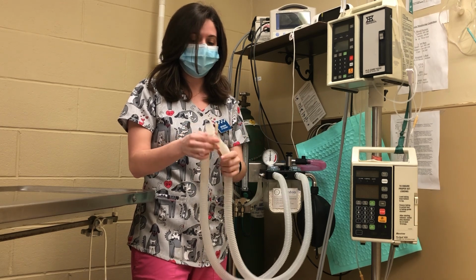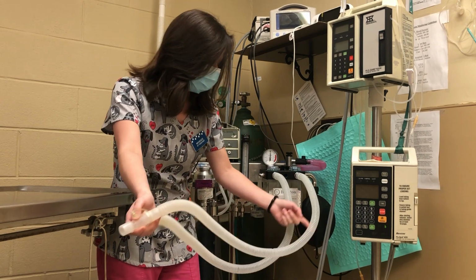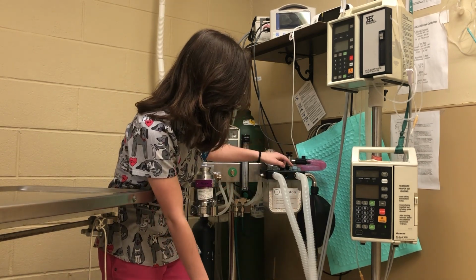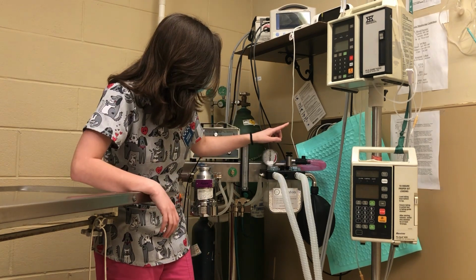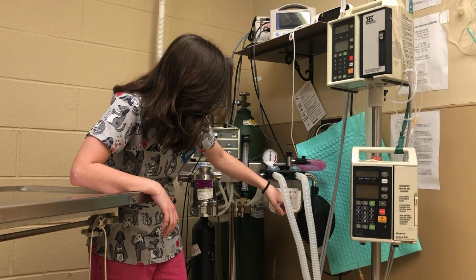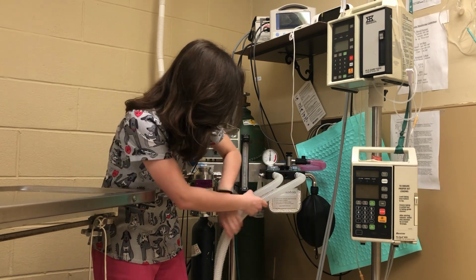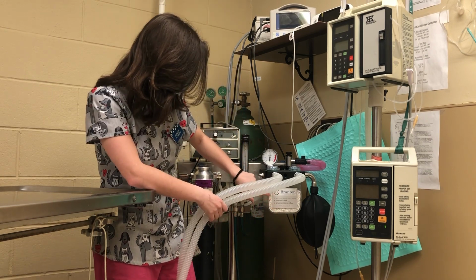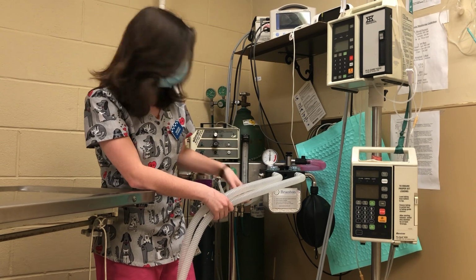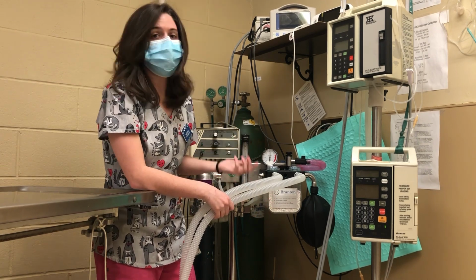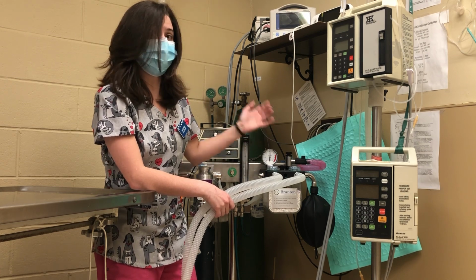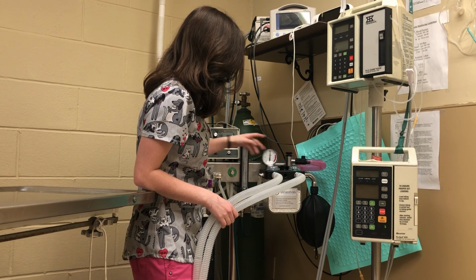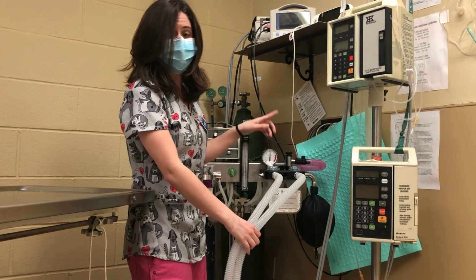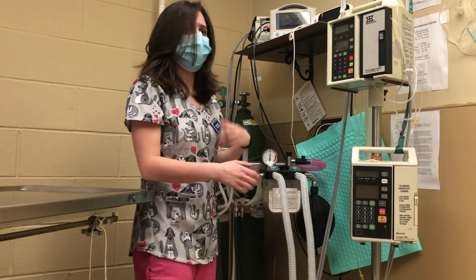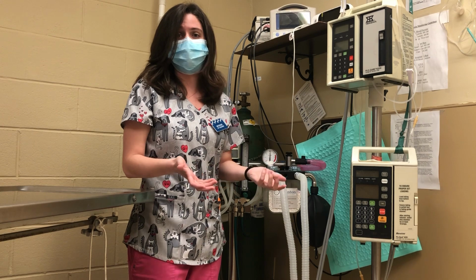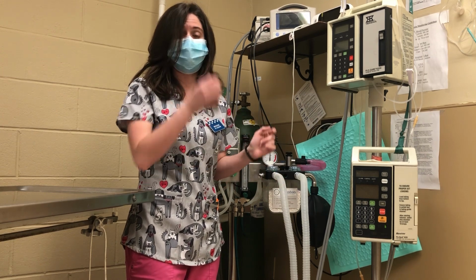That exits out the lungs into our Y piece, up the exhalatory tube, and then into our exhalation unidirectional valve. And then the carbon dioxide is taken out of there and deposited directly into our carbon dioxide absorber canister. It's filled with soda lime, which is absorbent granules, all these granules here. And this absorbs the carbon dioxide so that it doesn't re-enter the system and the patient isn't rebreathing it. And then the rest of the gas is circulated back, and it goes into a big circle once again where it's being inhaled and exhaled. So essentially they are rebreathing the same air that they inhaled and exhaled, minus carbon dioxide.